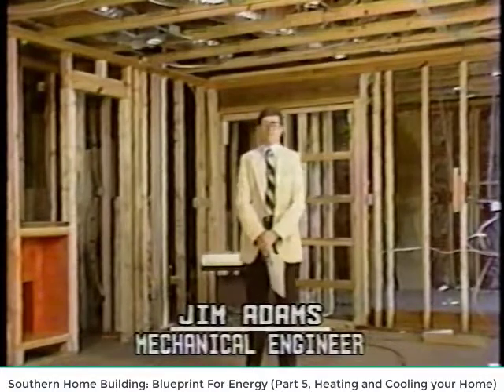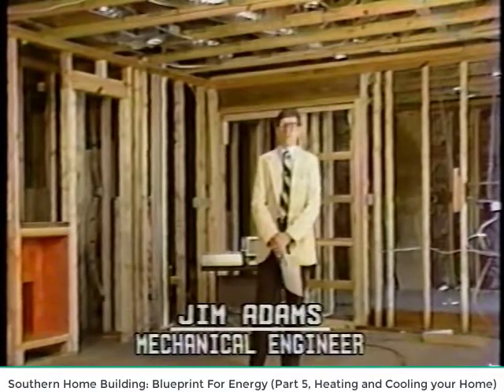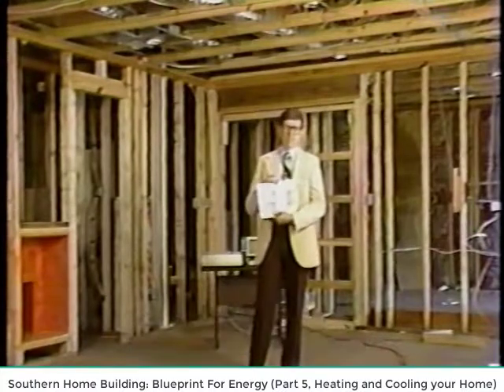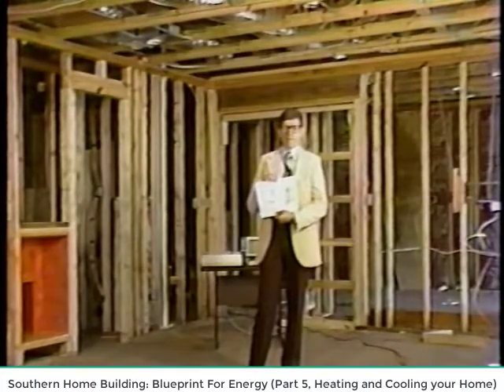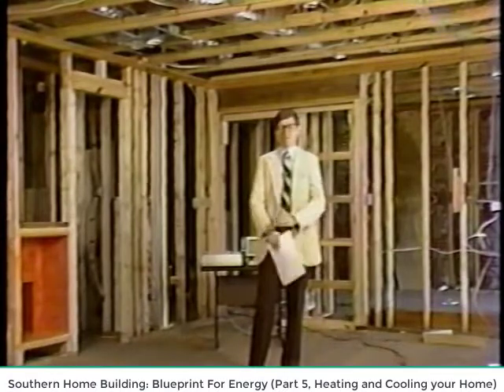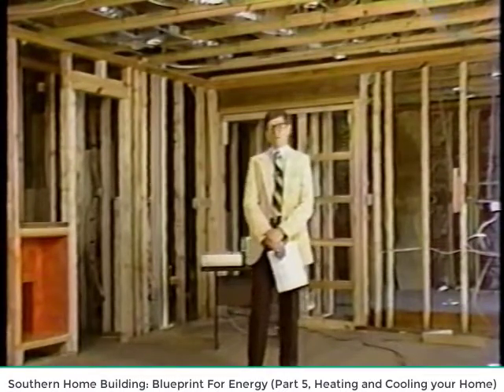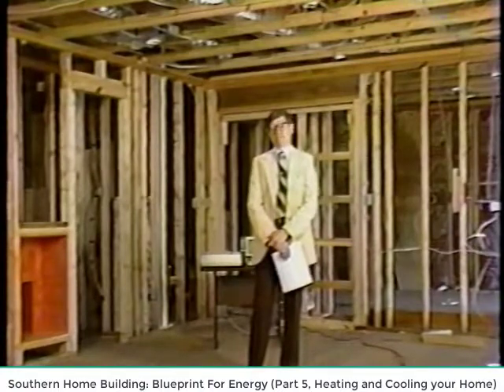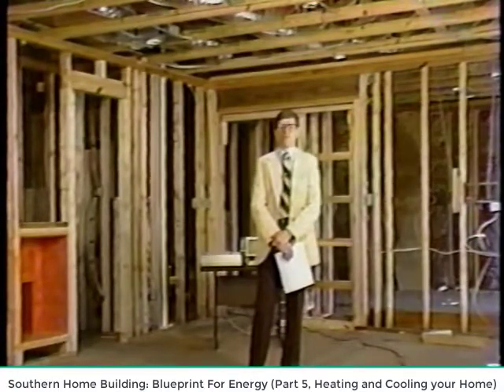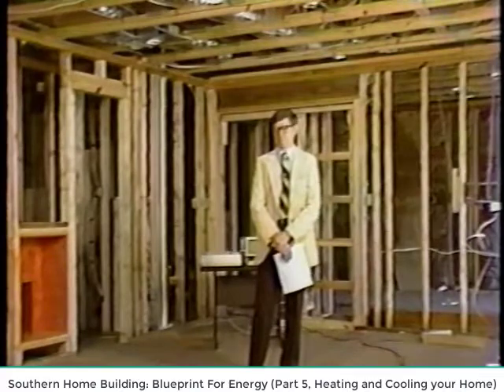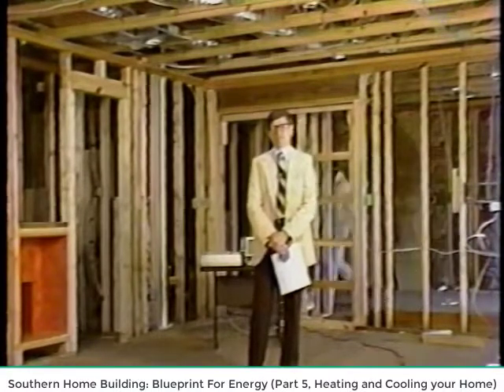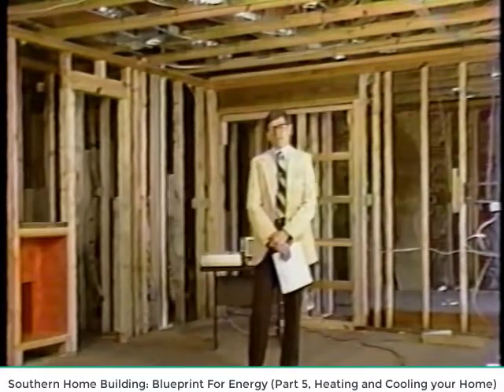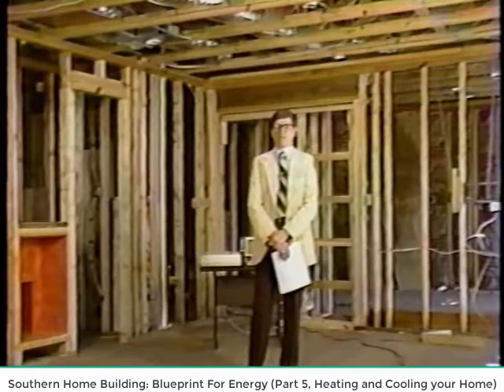The proper method of sizing the HVAC equipment is to use a heat loss, heat gain form, such as this. A form such as this has a lot of numbers on it, but there's very few numbers really used in the calculations, and it's fairly simple once the size of the windows, doors, walls, and so forth is obtained.